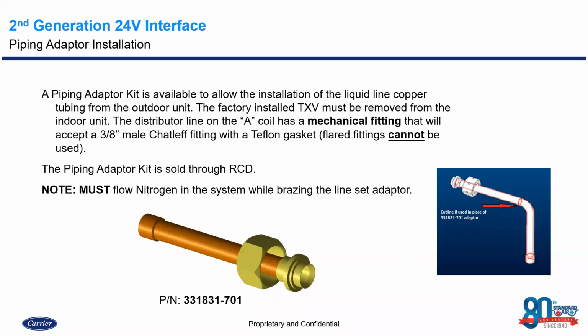So again, if you're not doing the press fittings, you need to make sure that when you are brazing, you are flowing nitrogen. It doesn't have to be a ton, just 1 to 2 psi. And again, that should be something in your refrigeration process when you're doing brazing. That should be the ABCs of that: flowing nitrogen while brazing.